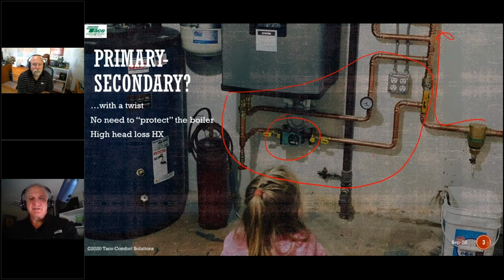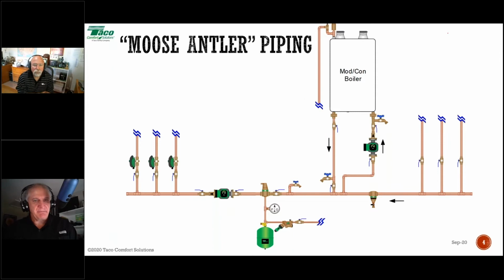I like to refer to this as the boiler piping or the boiler loop, and then the other loop as the distribution loop. And what we call this thing in general is what we call moose antler piping. So moose antler for obvious reasons. You get your moose antlers. There's your moose head and there's your antlers, right? But this piping right here, that's your distribution loop or your heating loop. It's the delivery loop that delivers the heat to the structure. And then the boiler loop is simply the piping that connects that distribution loop to the boiler. So again, whatever you want to call it is whatever you want to call it, but I just want to make sure we identify the terms.